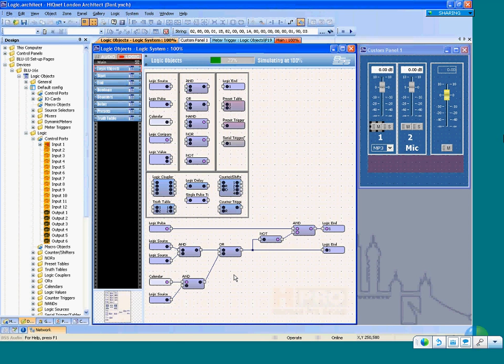And if you want to get even fancier, you can use the momentary contact switch so they can't accidentally leave it on. They trigger the momentary contact with the key, and we set up a logic circuit that'll go on and lock itself on and reset itself at 7 a.m., 8 a.m. So they can pop the key in, hit it, it's good for tonight. Or pop the key in, hit it, it's good for 4 hours. Whatever we decide to program. Very, very simple to do.